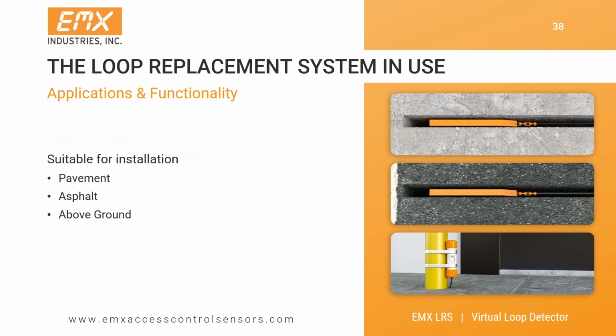The key in either install is that the system needs to be in a fixed, secure position. Once installed and calibrated, movement in the system can cause changes in the magnetic field and could cause false detections or false readings. So make sure it is fixed and not moving at all once it's been put into place.